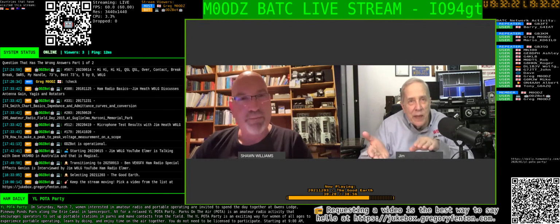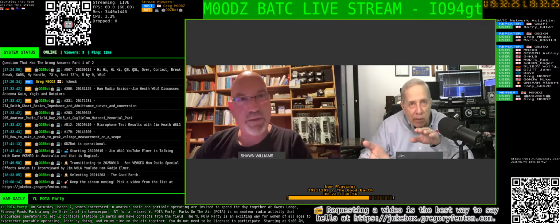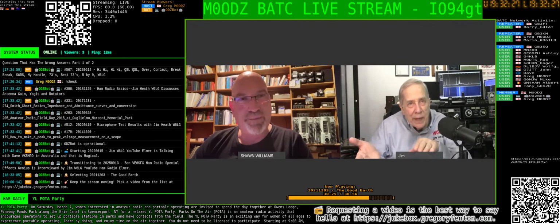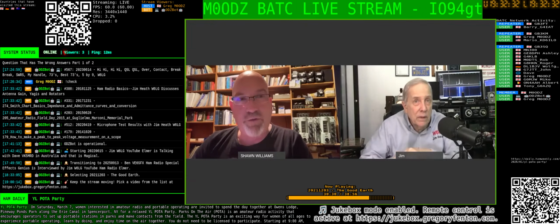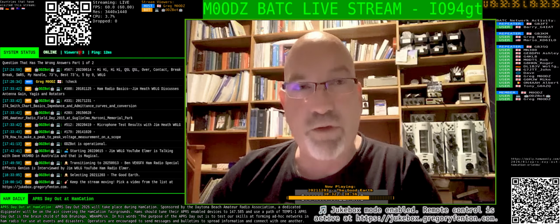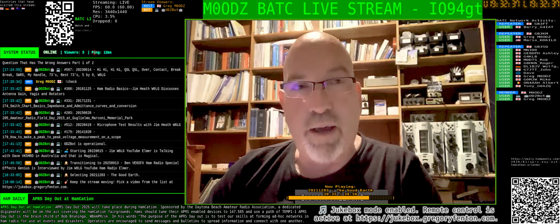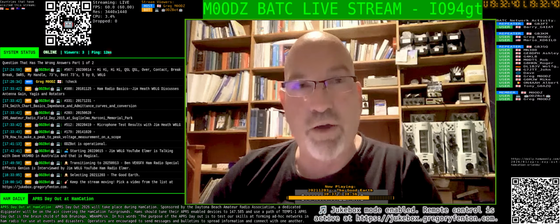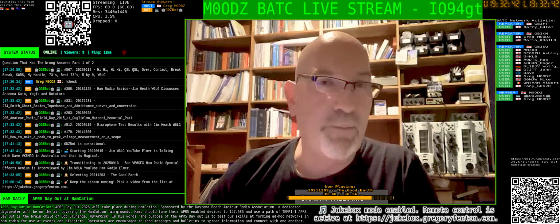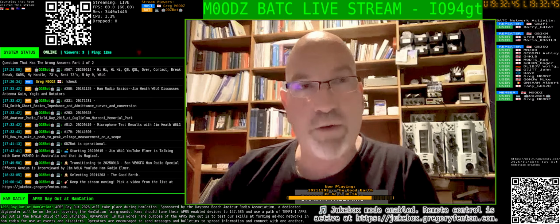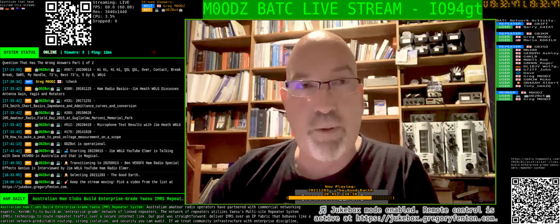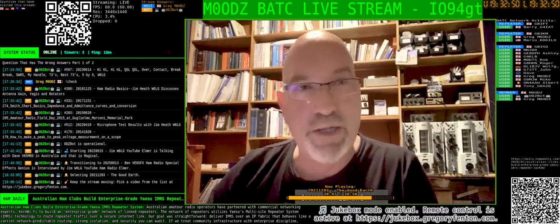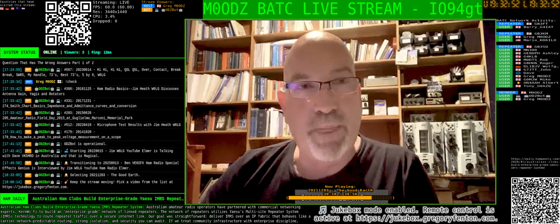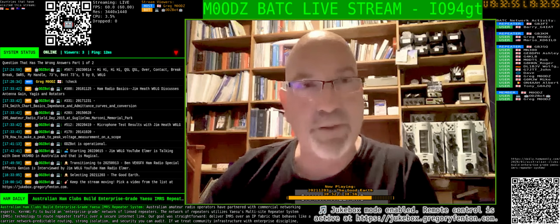You could have a difference in potential voltage between those two, and that could be a hazard that could kill somebody. So if you don't have a path to neutral on your station, and the Earth goes hot, it's going to end up at that auxiliary electrode. It's not going to trip a breaker because it's 4 amps or something on 110 volts. And if it's 220, it'll be around 9 amps. It's still not going to trip the breaker.